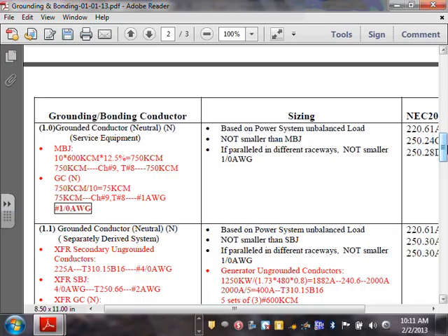So the unbalanced almost dropped that one. Not smaller than main bonding jumper. And if you parallel, do you guys remember the rule for parallel? Now I'm paralleling here. Can you parallel less than 1 aught? No. Can't parallel power less than 1 aught. That's the minimum that you can parallel. Everybody knows paralleling conductor, right?